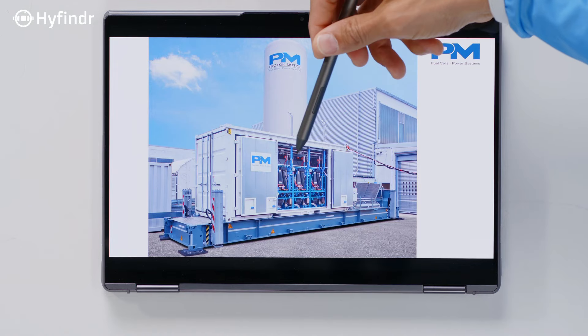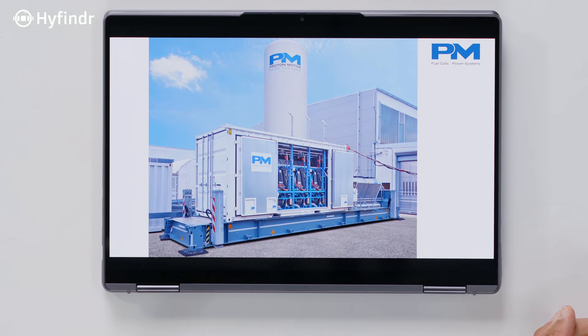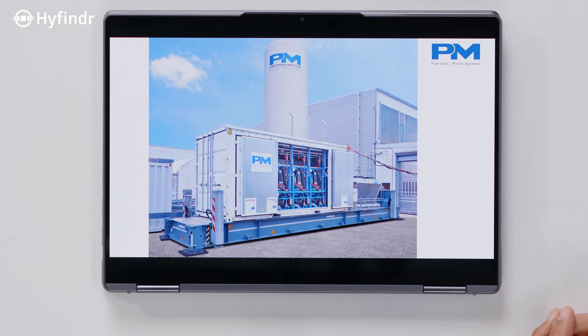You have three systems here — do they all run at the same load at the same time? If all of them run at the same time, they should run at basically the same load — this is also what the master controller takes care of. But of course you can have one system running and the others shut down. And this is also some kind of redundancy: if one system falls off, you have a little bit less load, but you still have power.